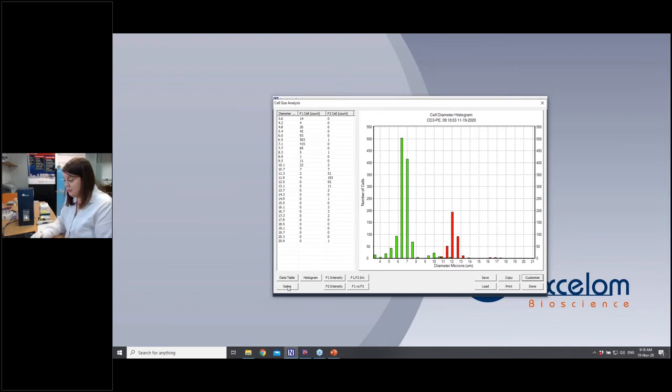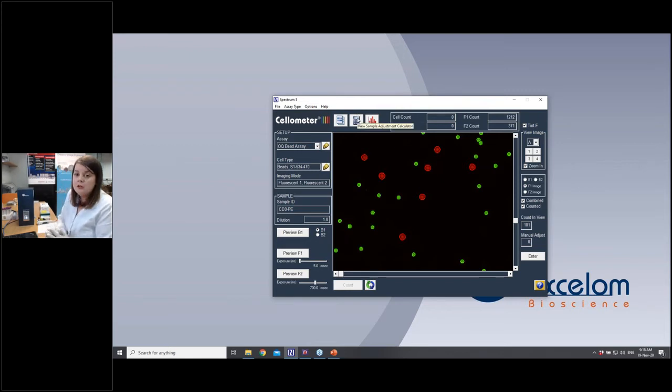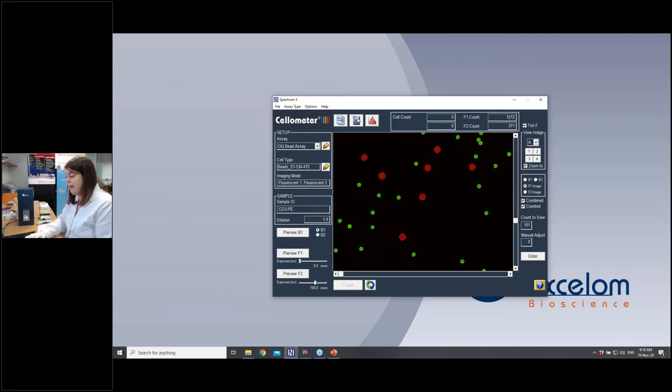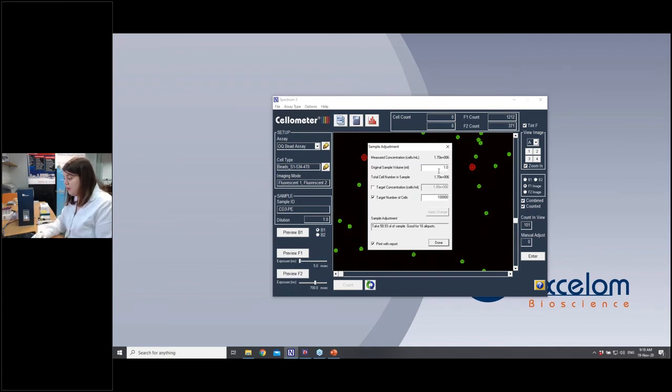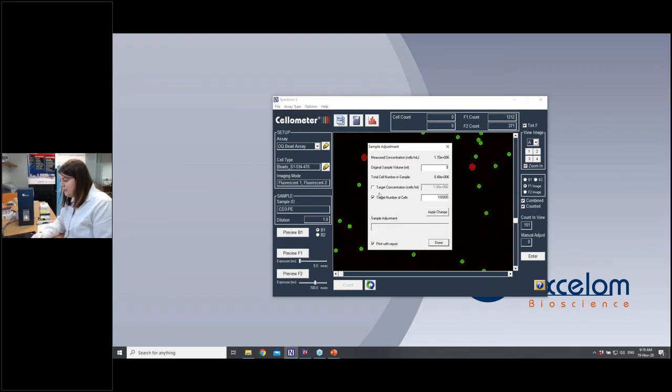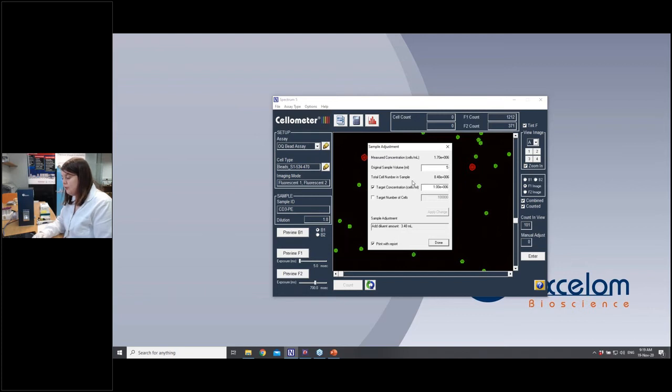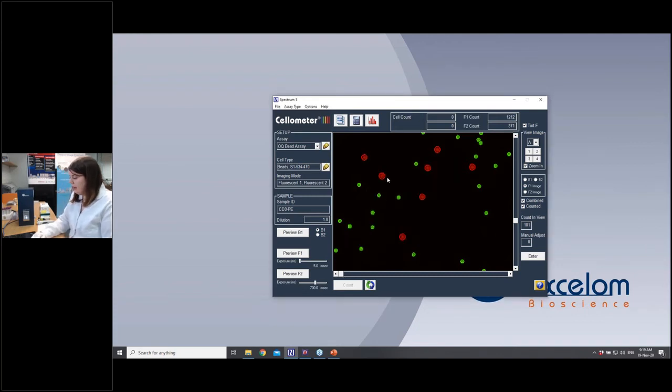There is another button here, the calculator button, which I really, really like, especially if you've got lots of people in the lab using the cell counter, looking at viability and then having to seed a flask after they've counted. So what the calculator will do is it will take into account your live concentration that it's just measured. You can tell it your volume of sample that you have. So let's say you have five mils of your sample and you can then give it a target number of cells or a target concentration. So let's say we wanted it at one times ten to the six and we have it at one point seven times ten to the six. If that is the case, it will tell you exactly how much diluent you need to add to your five mils to make a one times ten to the six solution for your next seeding.